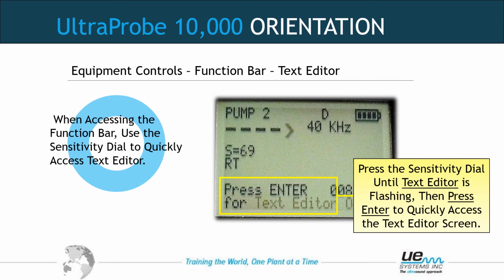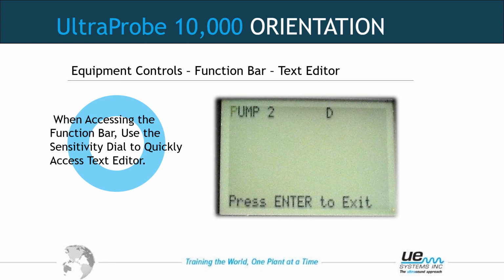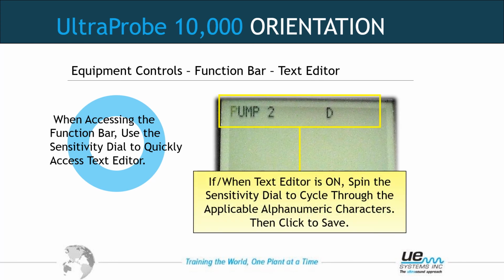So at the top of the screen, you see pump 2D. If it was off, this would not be there. You have 16 characters to name your machine and test point, or location and test point. This is typically done in the DMS software. If the press enter for text editor says on, then this will show up at the top of the screen. If you press the sensitivity dial right now, it would give you the option to enter in and change the name or add a name. Again, not good to do when you're in the field. We find it typically better to write down on a notepad and use the software. The option is here though.